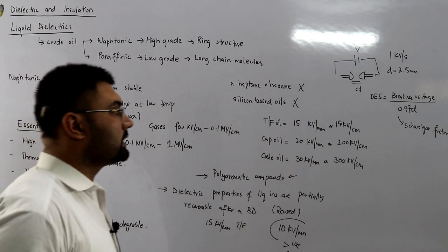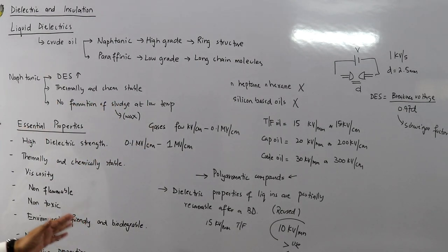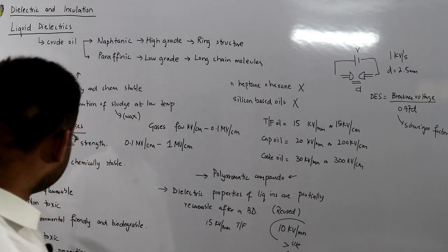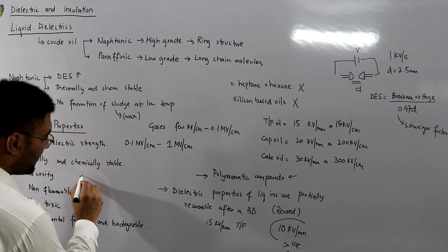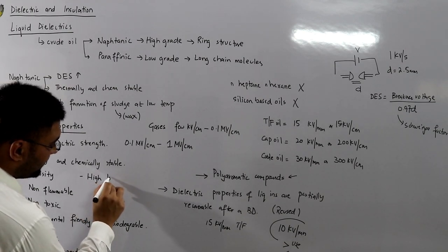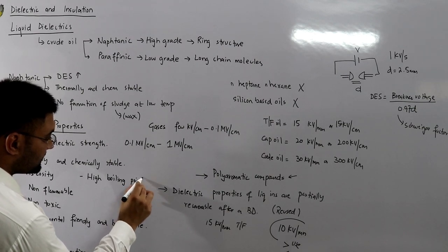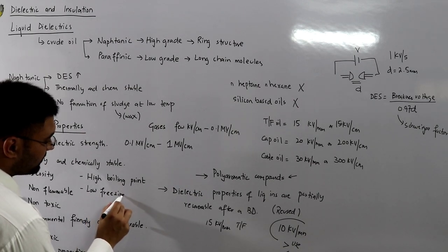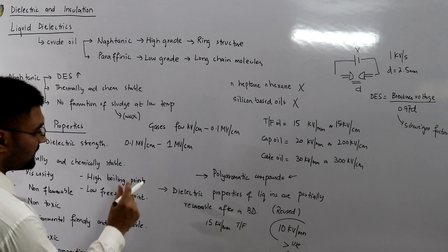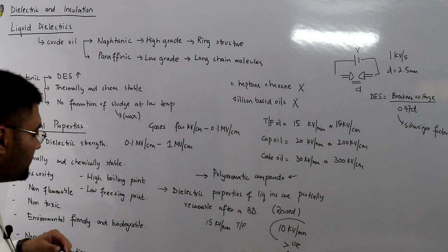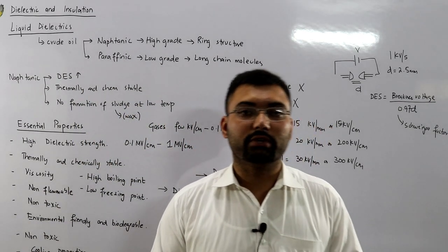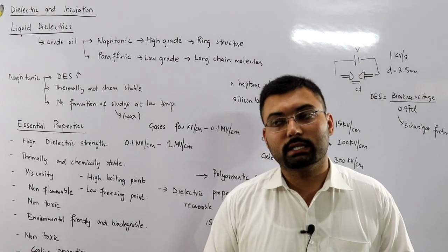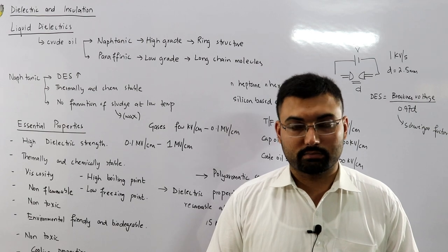To conclude, the essential properties of liquid dielectrics include high dielectric strength, thermal and chemical stability, appropriate viscosity, non-flammability, non-toxicity, environmental friendliness, biodegradability, cooling properties, a high boiling point, and a low freezing point. A high boiling point is needed for use in hot climates like Saudi Arabia, and a low freezing point is needed for cold climates like Russia. That is the introduction to liquid dielectrics. In the next video we will see the breakdown mechanism.